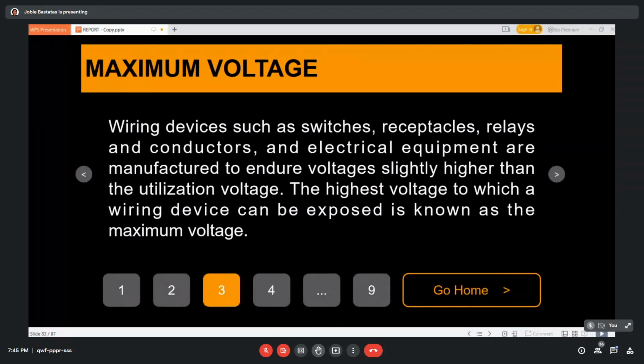So, wiring devices such as switches, receptacles, relays, and conductors and electrical equipment are manufactured to endure voltages slightly higher than the utilization voltage. So the highest voltage to which a wiring device can be exposed is known as the maximum voltage. So it doesn't mean, guys, na if ma-reach sa ato ang utilization voltage ang maximum voltage, quickly mo turn off na imong system.